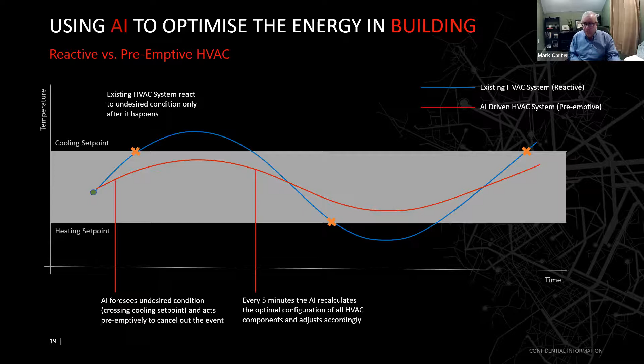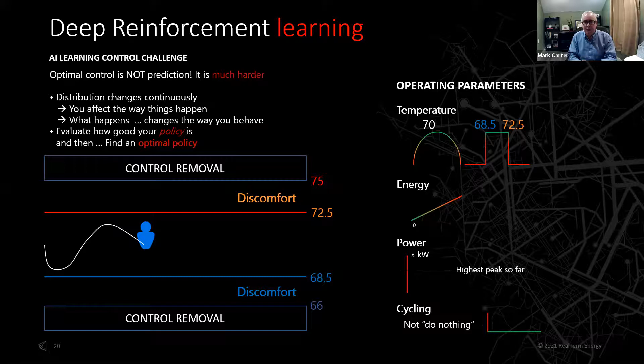But prediction is actually a lot easier than the actual control, because once you start making control moves, now you're actually affecting the future. So it does have to take a look at different operating parameters. So imagine not only is it looking at the temperature, but it's also looking at your energy utilization. If you have any peak power rates, you don't want to exceed that, which could cause your building to pay for higher energy throughout the entire month if you hit a particular peaking rate. And it also doesn't want the system to cycle, warm and cold. So it's looking to balance all those four operating parameters to have the most efficient system possible.